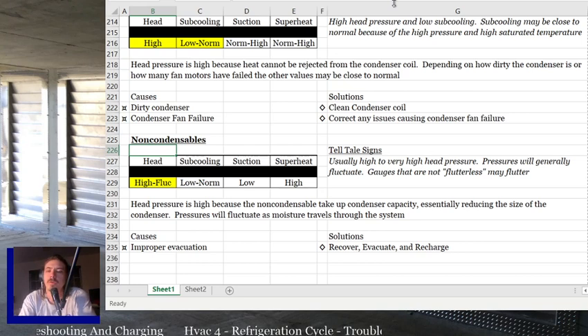You might clean the coil, and you might try and pull out some charge, and your superheat's still crazy high and nothing's seeming to fix anything. And your superheat's usually high, so you shouldn't be confusing it with an overcharge anyway, but it happens. But the really high head pressure and the fluctuating head pressure are usually the signs that tell you you've got non-condensables. The head pressure is high because the non-condensables take up condenser capacity, essentially reducing the size of the condenser.